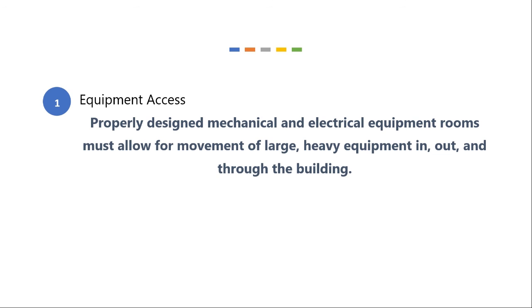It's important that the mechanical and electrical rooms in the building allow you to move large, heavy equipment in, out, and through the building. So that means you need a loading dock, you need a freight elevator, you need doorways that are wide and tall. And the reason is you need to bring in equipment, tools. Sometimes equipment breaks down and has to be replaced. If you can't bring new equipment in to replace what's broken down, then you're going to fail.